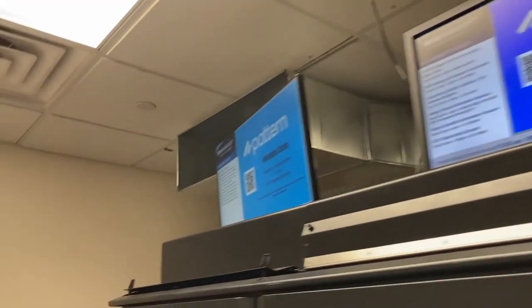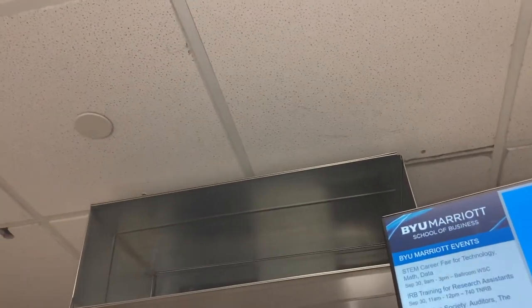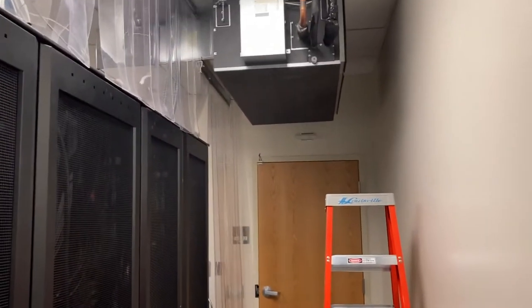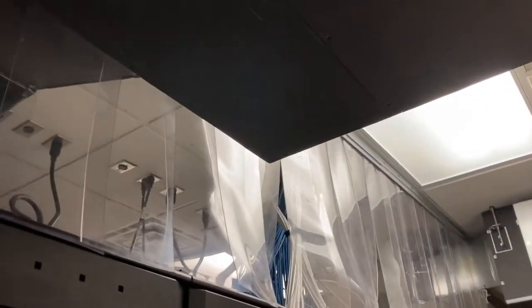Speaking of airflow, IT equipment runs hot and the rooms need air conditioners. Here you see air conditioners blowing cold air into the cold aisle of the server room. IT equipment frequently has fans on its front side that suck in cold air to cool off with, and the equipment pushes the hot air out their backsides. In this room, a plastic curtain separates the cold aisle and the hot aisle. The hot aisle is significantly warmer in temperature than the front side.